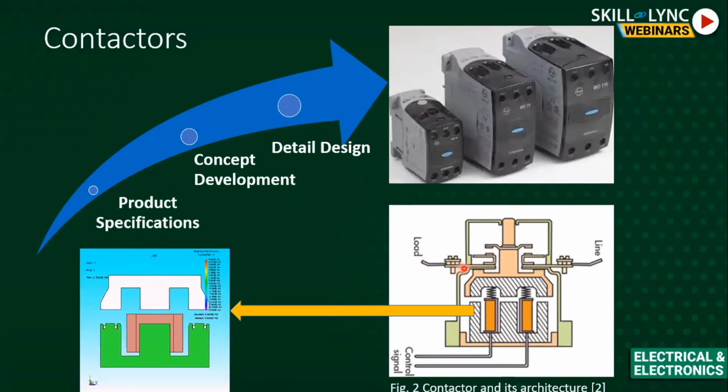So if you see, this is the fixed contact, this is the moving arm. Moving arm is connected to your electromagnet, this moving electromagnet. So initially when we are just starting out the design, we would know, okay, this much force this magnet is supposed to generate so that it can start the travel and it can bring this entire assembly down. So if you see this analysis, this is how the initial specifications of this electromagnet were made, and then FE analysis is run to check whether the magnet is able to travel fully.